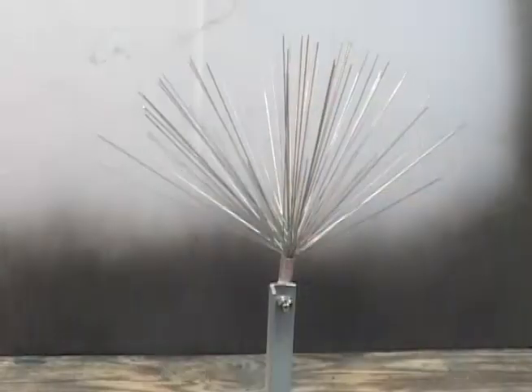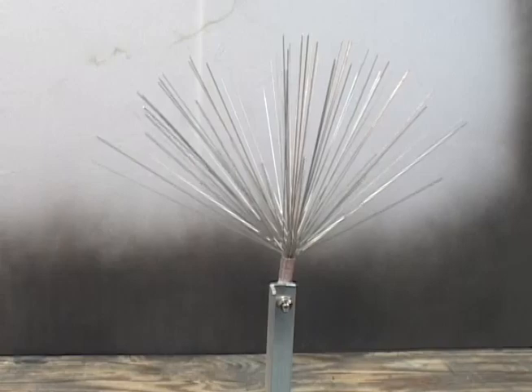It's a tiny stream of electricity that actually flows into the air. The only thing Franklin didn't have was the instrumentation to measure how much that electric current was. We have learned over the years that if you put a large number of points pointing up into the air, it has adequate capacity. His lightning rods sometimes attracted lightning rather than discharging, so the technology nowadays is to put a whole lot of points up there and bring the electric field voltage down below the threshold required for lightning.